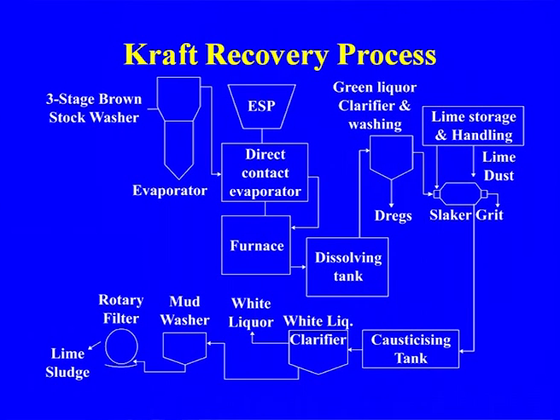The recovery furnace is very complicated. We are having the boiler part with three zones: drying zone, burning zone, and finally waste heat utilization in the boiler where we are generating steam. I will show the diagram of the furnace also. After that it goes to the dissolving tank where we are dissolving the smelt and the weak liquor coming from the causticizing section goes to the dissolving tank, where we are getting green liquor containing a higher percentage of sodium carbonate.